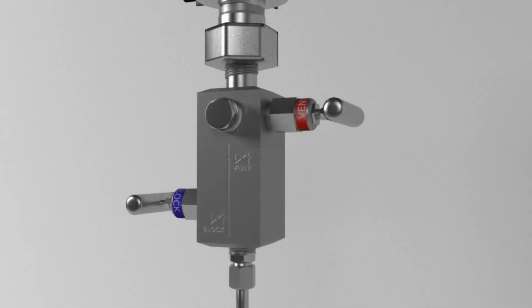So to perform a calibration, close the isolation valve, remove the cap to the vent port, open the vent valve, and make your connection.